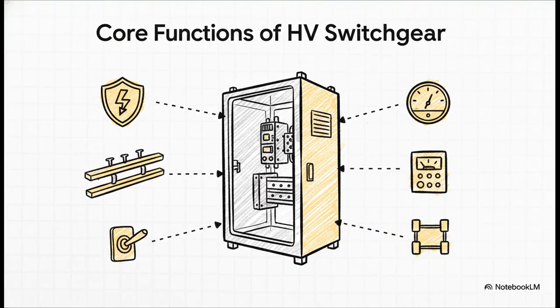So if you were to crack open an HV panel, you'd see that every single component has a critical job. You've got your protection gear, like massive circuit breakers. You've got the connection hardware, like bus bars, that actually move all that power around. And then you have your control switches, your measurement transformers to keep an eye on things, and of course, isolation switches to safely shut it all down for maintenance.